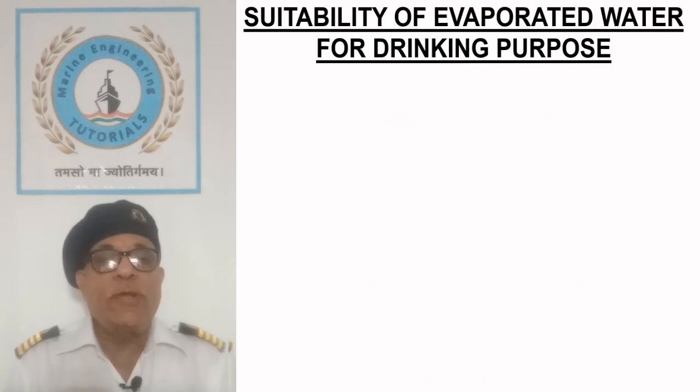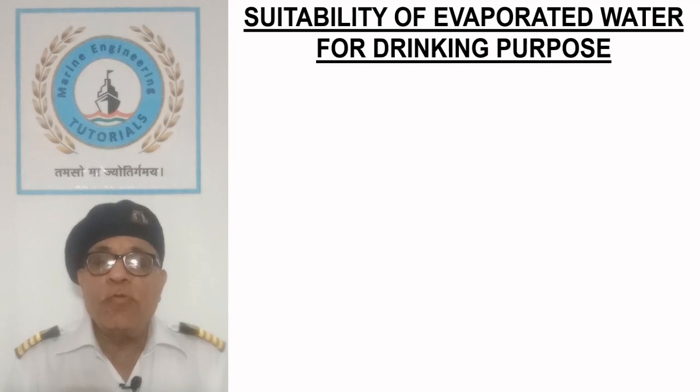Suitability of evaporated water for drinking purpose. Evaporated water on ship is nearly distilled with a very small amount of dissolved salts, below 10 parts per million. Water evaporated on ship is soft and deficient in minerals, thus it requires treatment before consumption.